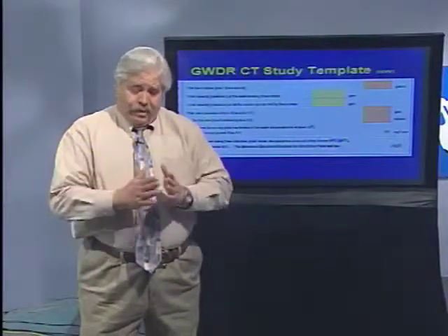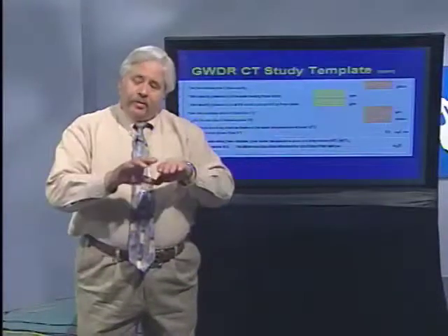Like I said, the well pump comes on at 16 feet and it continues to run until the tank fills back up to 22.5 feet. So it's going to run continuously during the period when the service pumps are running intermittently. So over this 4-hour period or over this 1-hour period, the service pumps and well pumps are balancing one another. The well pump runs continuously, the service pump runs intermittently. But the total amount of water moved by both the service and the well pumps is going to be equal during this period when water level is at the minimum.